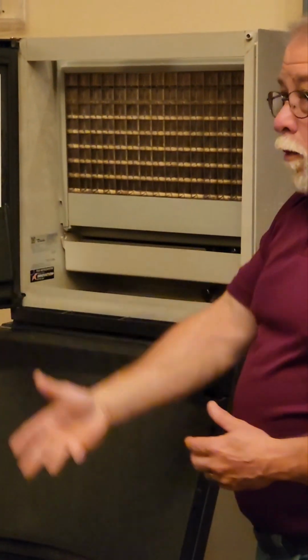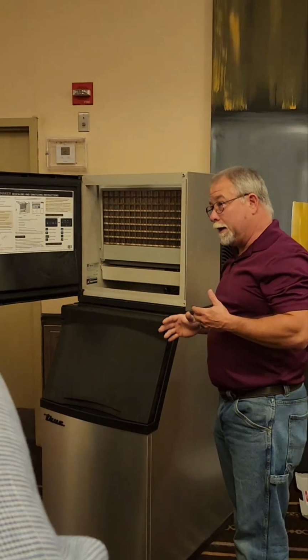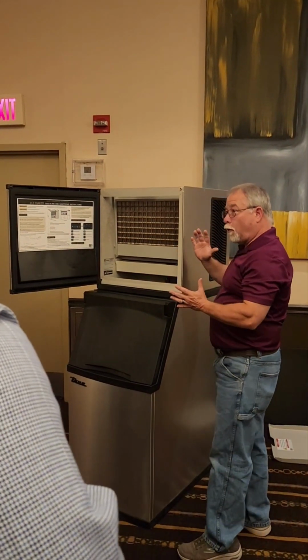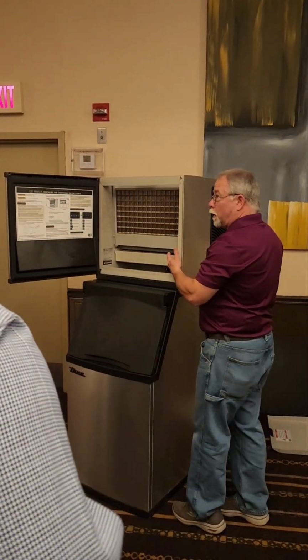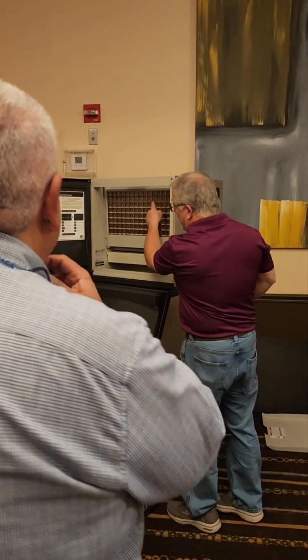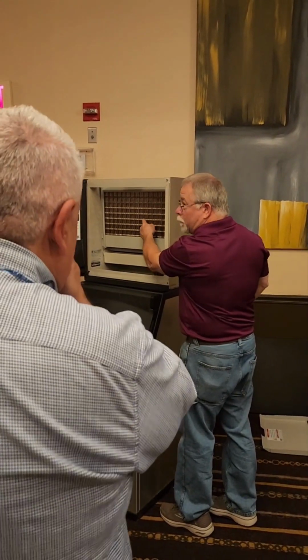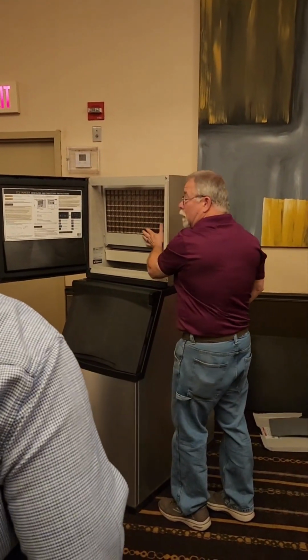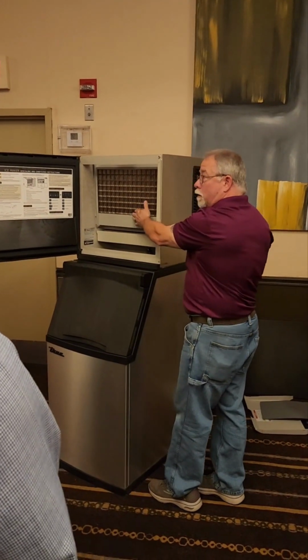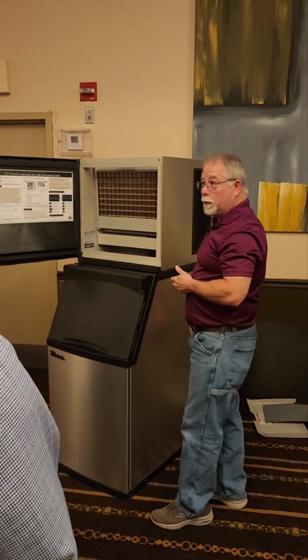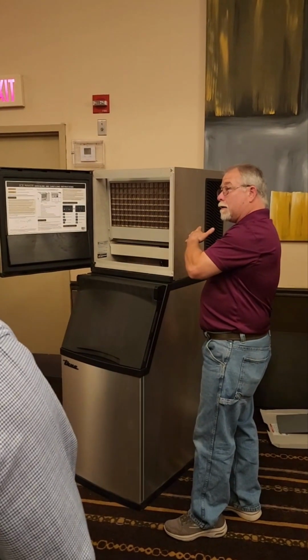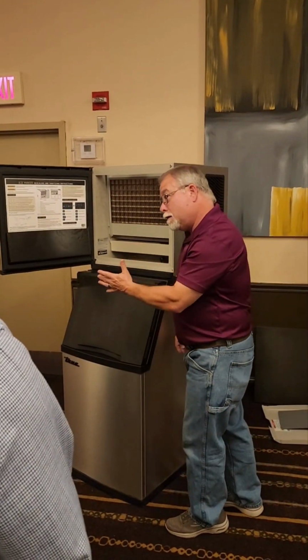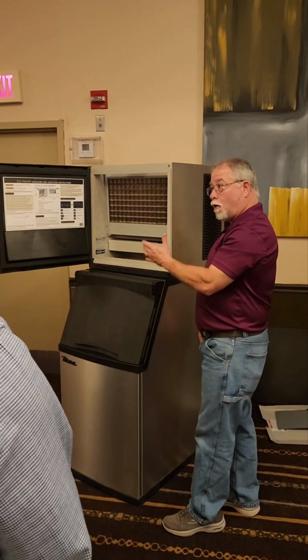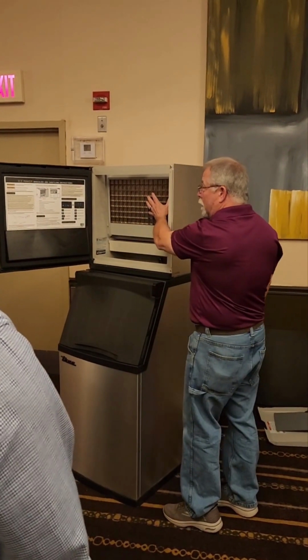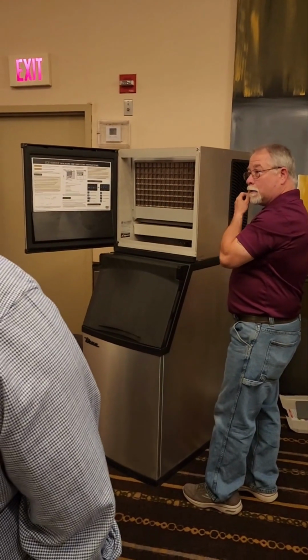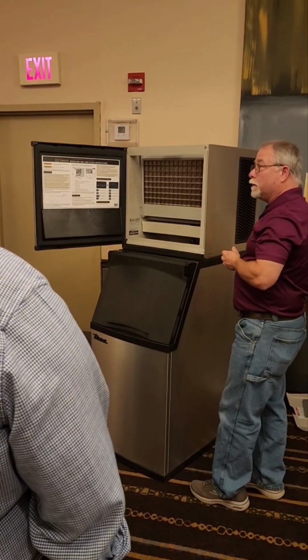So when we talk about leveling the machine with the legs -- if you have it tilted too far forward, at some point you're going to lose that capillary action grip, and it may start dripping off the evaporator way up here, and you might not have any water filling the lower cubes. If it's tilted too far back, it may not shed properly and you may get long harvest times, because it's battling gravity when it doesn't have the slope or angle that you need.